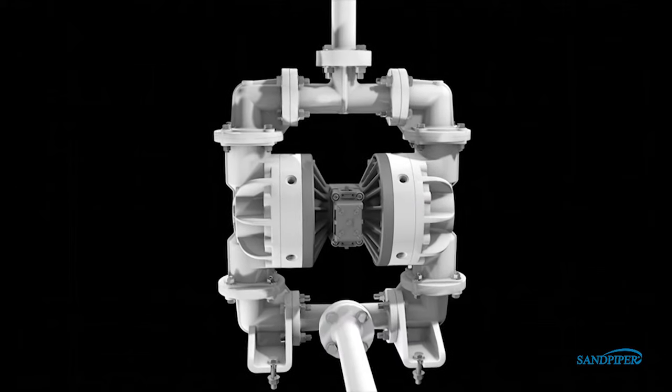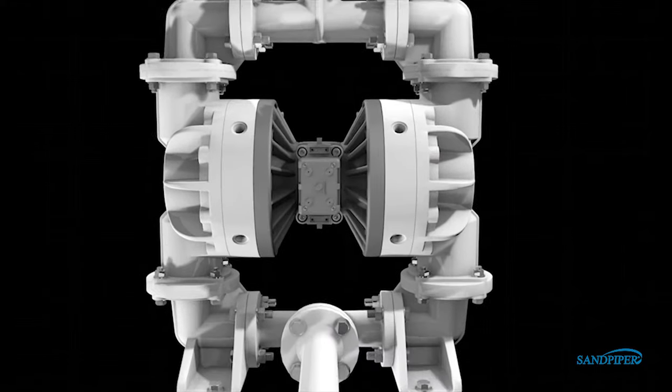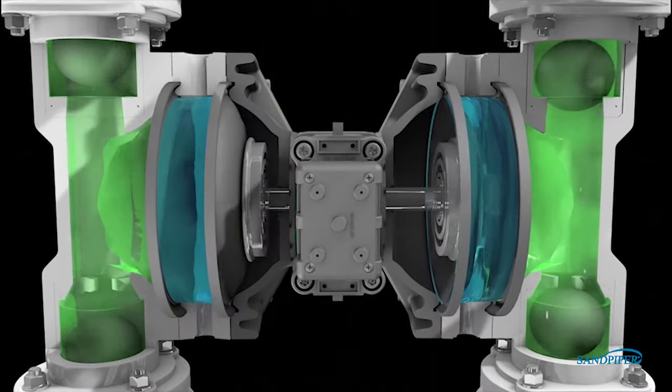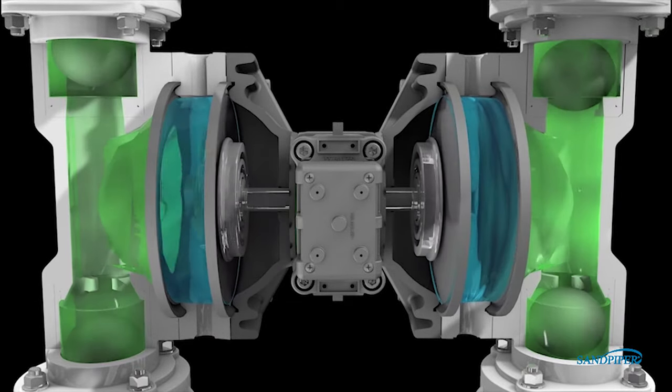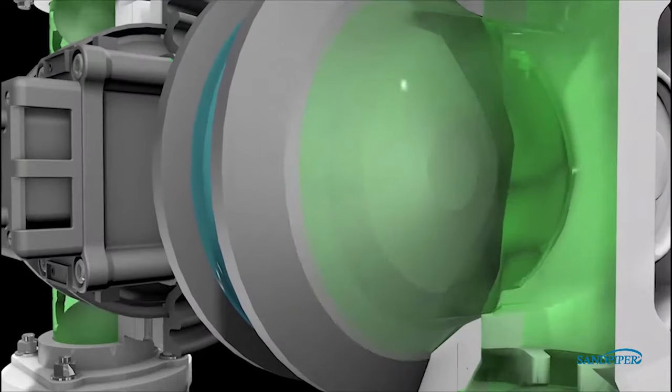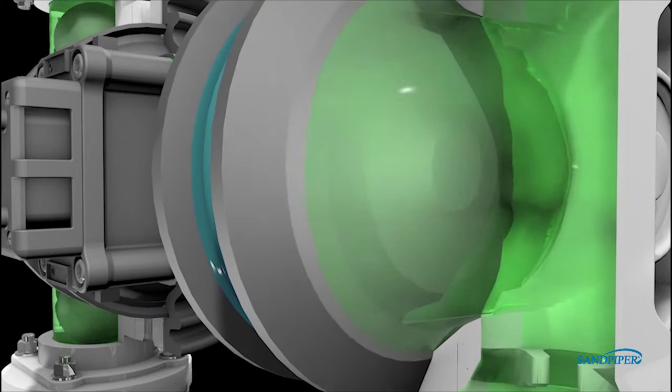All containment duty pumps are exclusively designed with containment chambers that are hydraulically balanced between the pumping diaphragm and driver diaphragm. The inner driver diaphragm and outer pumping diaphragm are locked into place with fill fluid that is void of air.